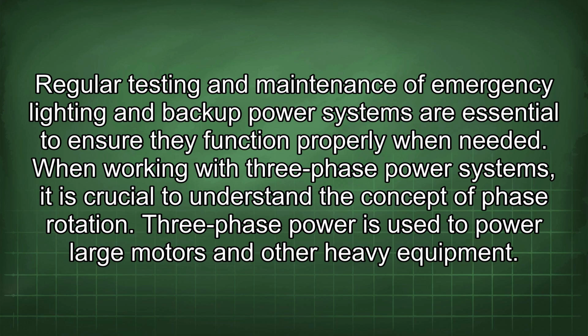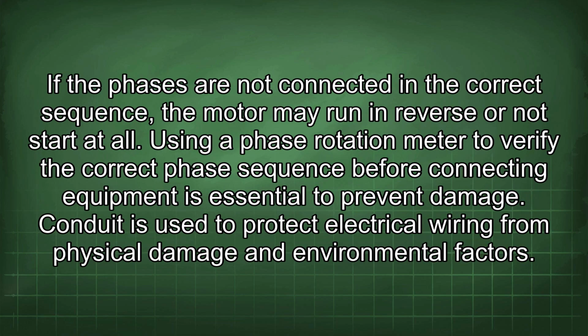When working with three-phase power systems, it is crucial to understand the concept of phase rotation. Three-phase power is used to power large motors and other heavy equipment. If the phases are not connected in the correct sequence, a motor may run in reverse or not start at all. Using a phase rotation meter to verify the correct phase sequence before connecting equipment is essential to prevent damage.